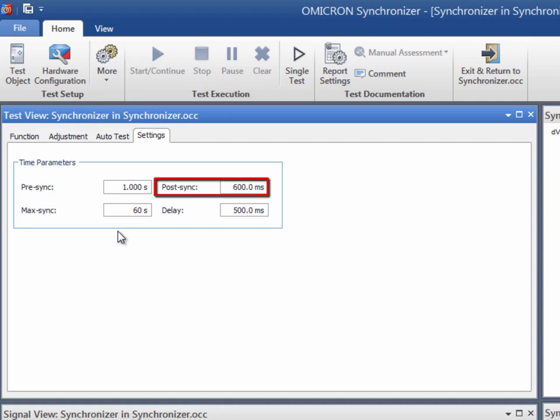The minimum post-synchronization time that can be input depends on the start release type defined in the test object. If set to continuous or none, the minimum post-synchronization time is the CB closing time. If set to pulse, as in our case, the minimum post-synchronization time is the higher value between the circuit breaker closing time and 500 milliseconds, which is the pulse duration issued by the synchronizer. If no synchronization is achieved, a release signal is sent to the relay and the test for this point is finished.